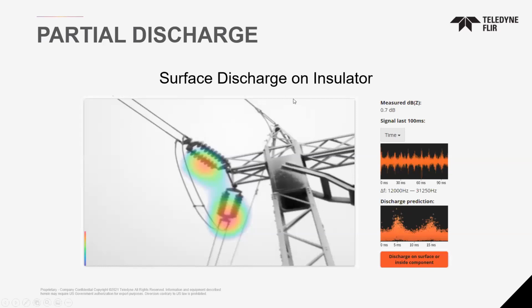Here again, another surface discharge on the insulator. You can actually see a little bit of vibration, and you can set these cameras to see 3 different hotspots at once. Here we have again discharge on the surface or inside the component. And the other nice thing, as you can kind of see from this image, these cameras have a range of 100 meters, over 300 feet.